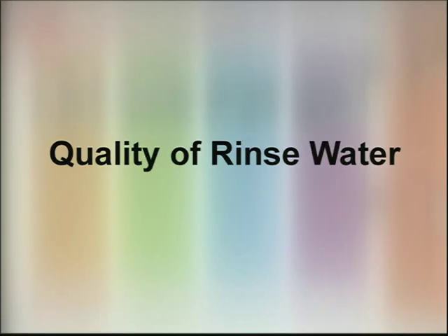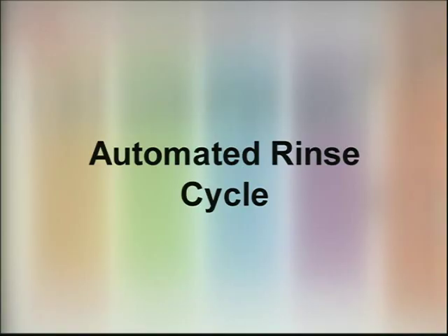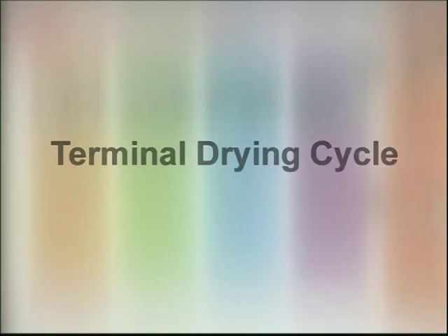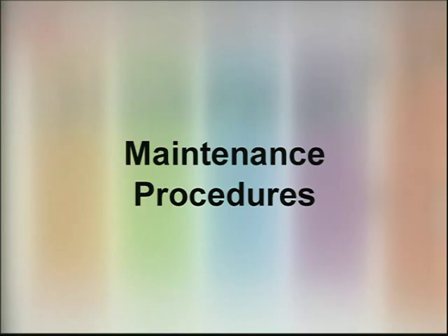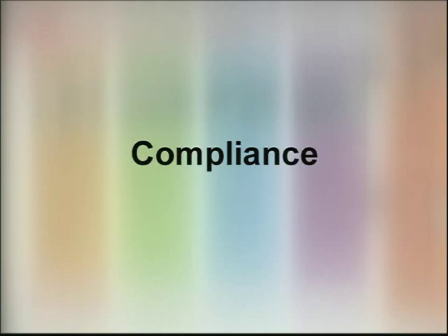The microbial quality of the rinse water. The inclusion of an automated rinse cycle. The inclusion of a terminal drying cycle that removes residual water fluid from within the scope channels. Maintenance procedures for water filter replacement and/or decontamination of the filtration system to ensure microbial quality of the rinse water, etc., and compliance with local and federal regulations and/or national guidelines.